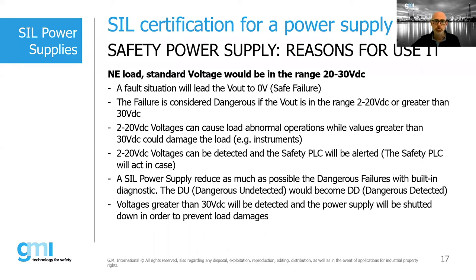Now, we introduce the concept of safety power supply applied to a typical application as energize to safe or de-energize to safe. As we know, typically safety systems are designed to remove power from the system, typically the de-energize to safe application. Therefore, the failure of the power supply, which goes to zero output voltage, is considered a safe failure. So we assume that all safety functions are of the de-energize to safe or de-energize to trip type.